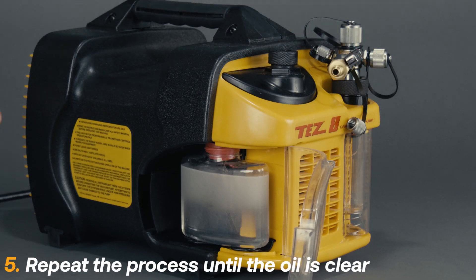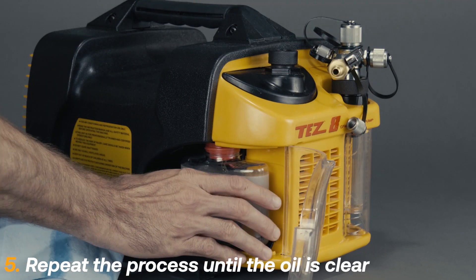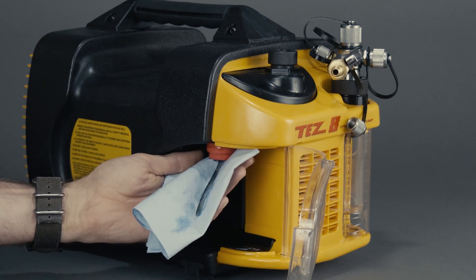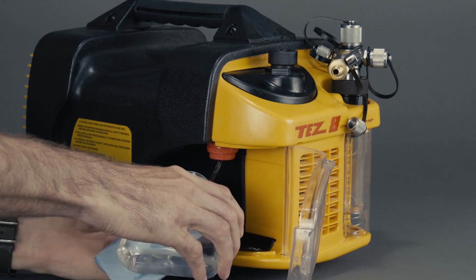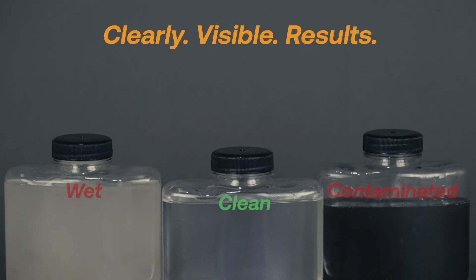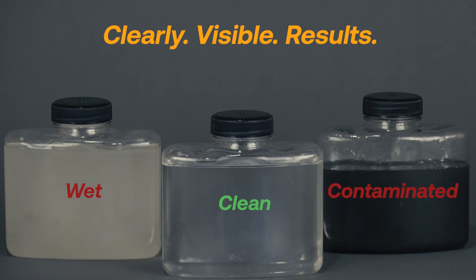Excess moisture or contamination will require additional flushing, so repeat the process as needed. Run the machine until the oil stays mostly clear for five minutes. The TEZ-8 cartridge makes monitoring oil easy with clearly visible results.